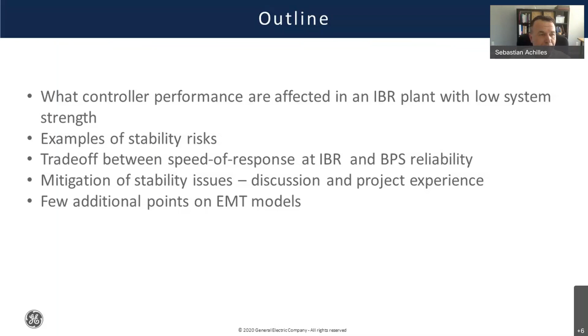So this is for a wind plant, but actually it's not too different for other plants. In a wind plant, each wind turbine will have a converter control and a turbine control, and then typically the full plant will have a single plant controller that takes measurements from the point of interconnection. So you have at least three types of controllers. If you look at solar or battery, it's not that different. In some cases, the converter control and the prime mover related functions may be in the same controller, and in some cases you may have two, also for batteries and for PV. So this is quite representative of what you may find.